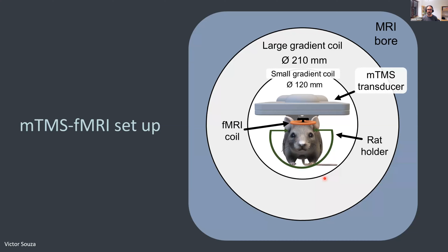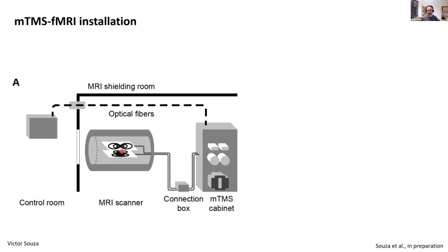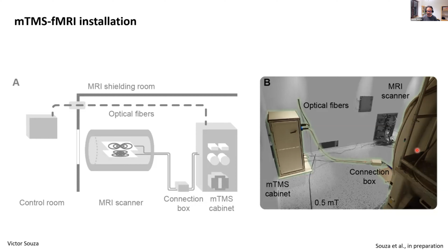We built and installed the cabinet for the stimulator inside the MRI shielded room, and the device can be controlled right next to the computer that also controls the MRI. From our cabinet, we have cables running to the coils that are placed inside the MRI. This is a photo of the setup there in Kuopio. Highlighted here are the cabinet fixed on the wall in the corner, the optical fibers that go to the control room, and the connection box that allows us to connect the transducers that go to the MRI.